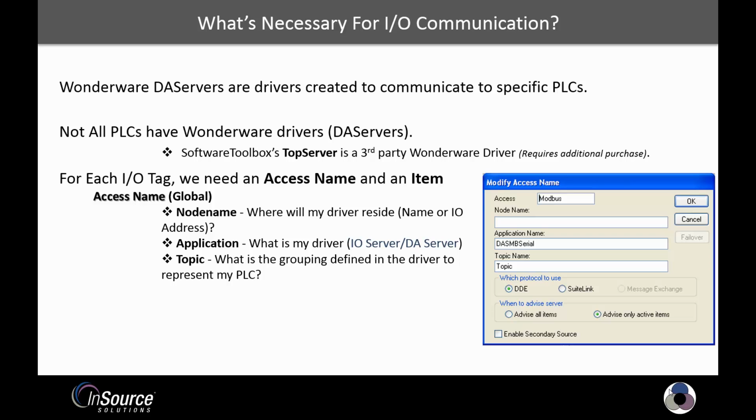A few other things that we define in an access name for an InTouch I/O tag is the protocol. What type of protocol will it use to communicate to the driver that talks to the PLC? Is it going to use DDE, or Dynamic Data Exchange, which is kind of a dying protocol, or will it use the Wonderware SuiteLink protocol? An access name can also use the open protocol known as OPC, which is a Microsoft standard. There are some drivers that only speak the OPC protocol. InTouch can communicate to those OPC drivers.